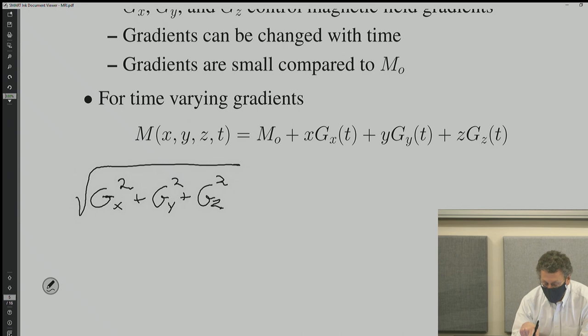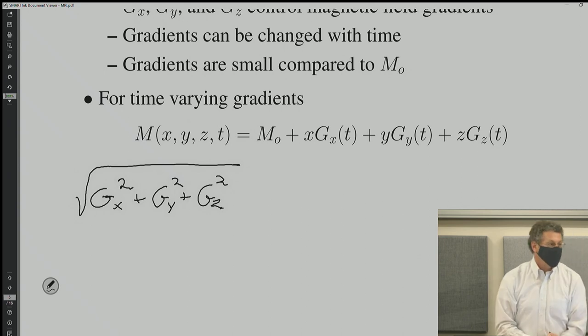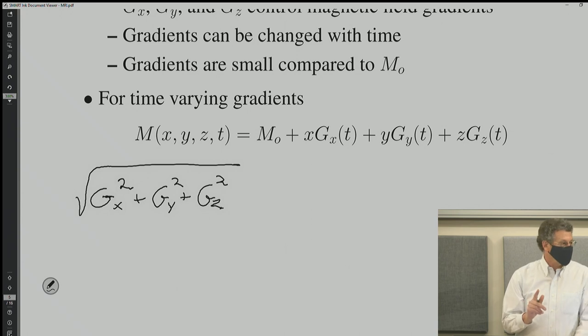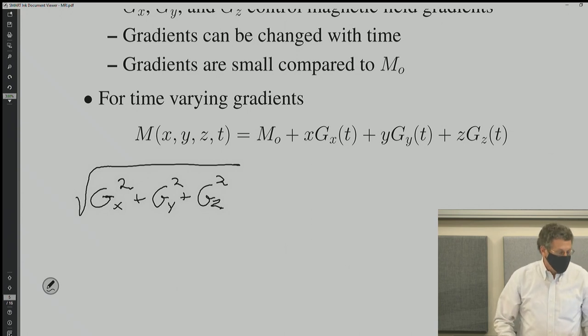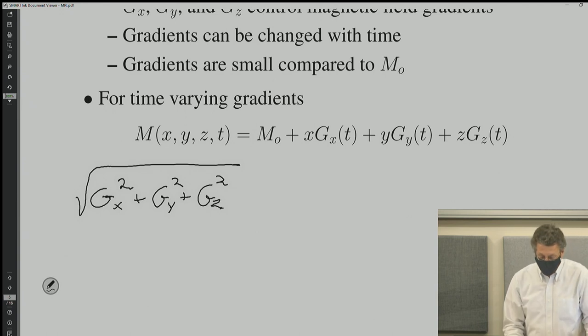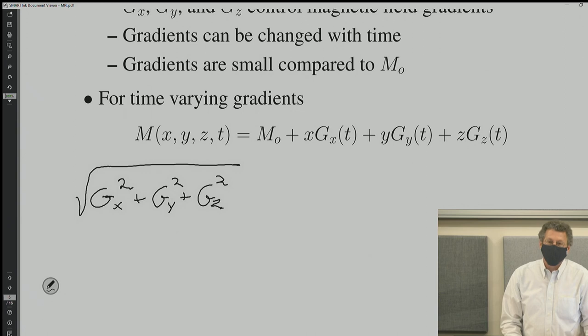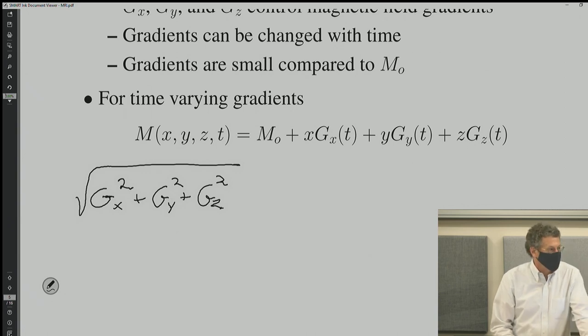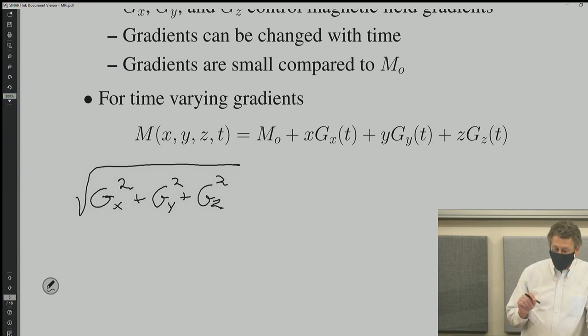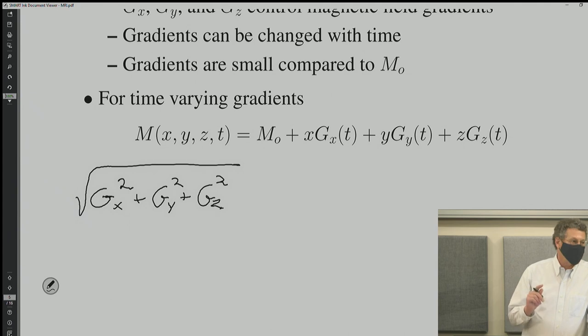The maximum gradient strength is important because the FDA regulates it — specifically, it's the rate of change of the maximum gradient strength that's regulated. The reason is this: if you have a changing magnetic field, it creates an electric field. That's how a motor works — in a coil, if you push a magnet in and out, it causes a current in the wire.